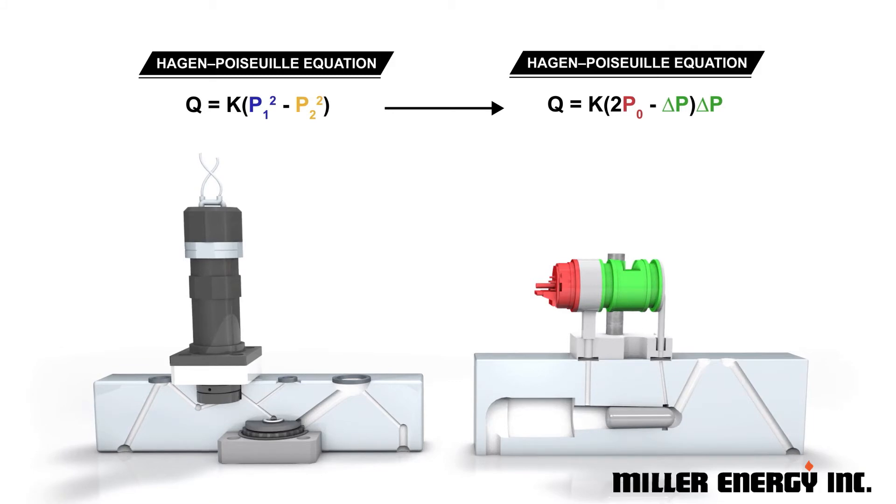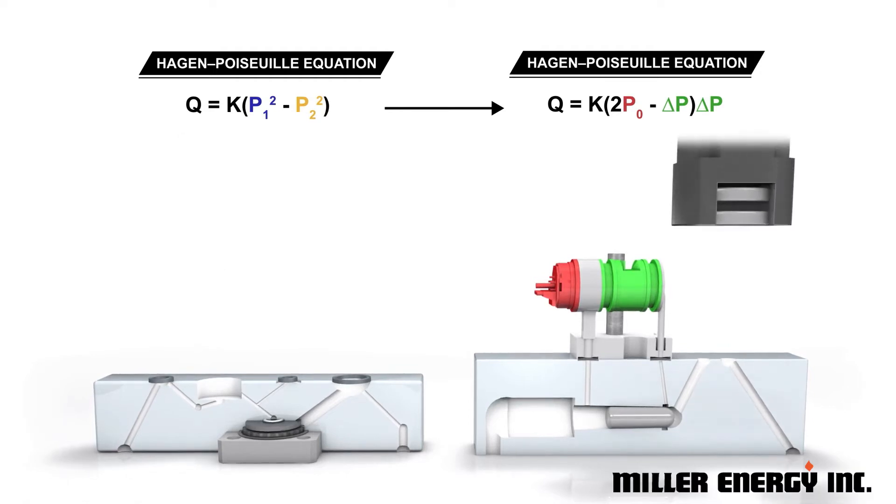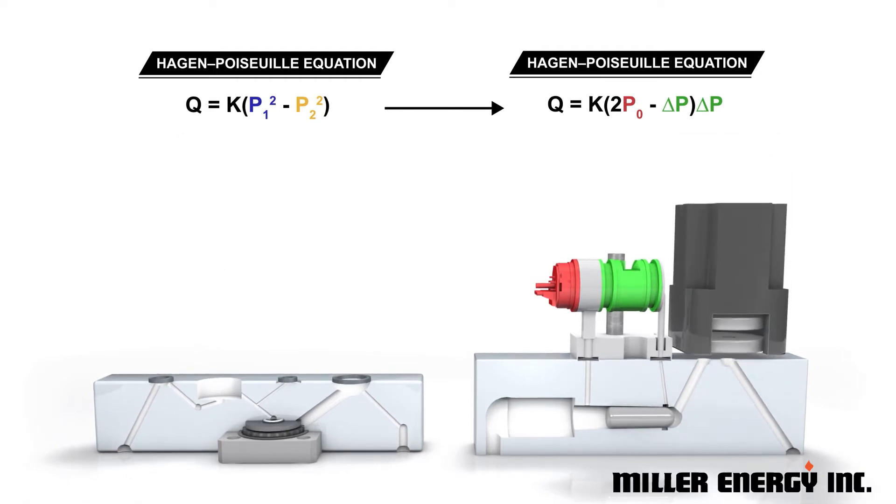The GP200 replaces the need to match P1 and P2 by using a true differential pressure sensor. By rewriting the equation, we're able to measure the true differential pressure versus a derived differential pressure using discrete P1 and P2 values.